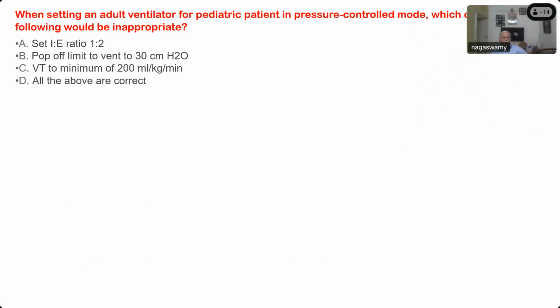Okay. When setting an adult ventilator for a pediatric patient in pressure control mode, which of the following would be inappropriate? The setting of I:E ratio at 1:2, pop-off limit to 30 centimeters of water, tidal volume to a minimum of 200 ml per kg, respiratory rate per minute. All of the above are correct. Tidal volume, C, sir. 200 ml per kg. Normally, do you give 200 ml per kg for one respiration? Normally, we set it at how many ml per kg? 6 to 8 ml per kg, sir.